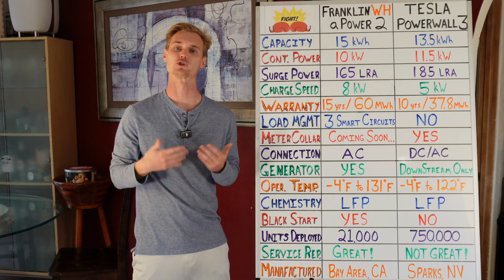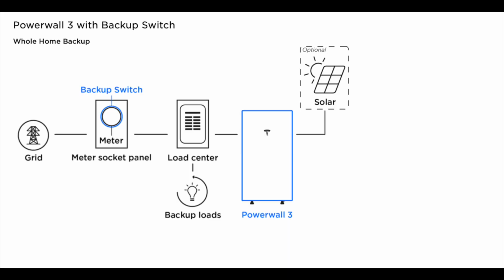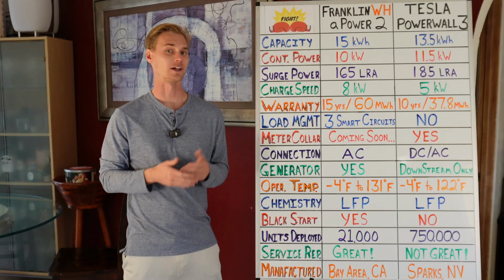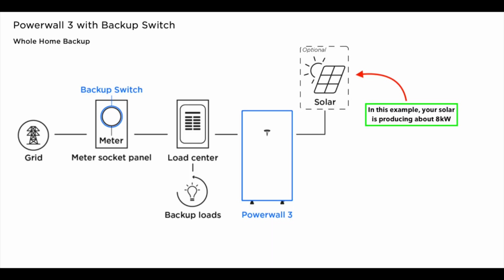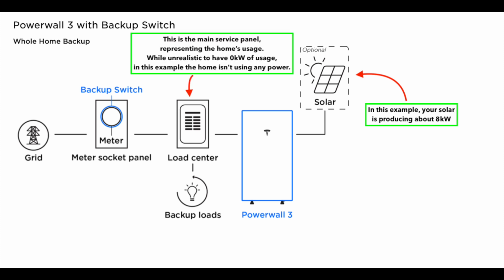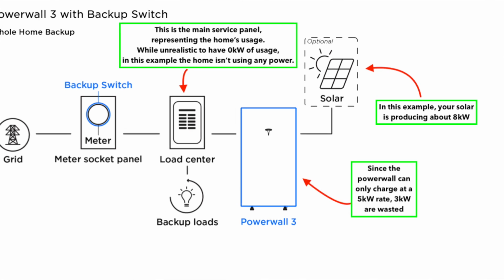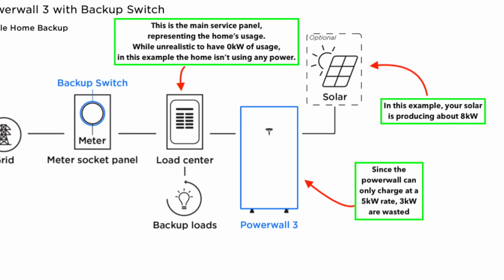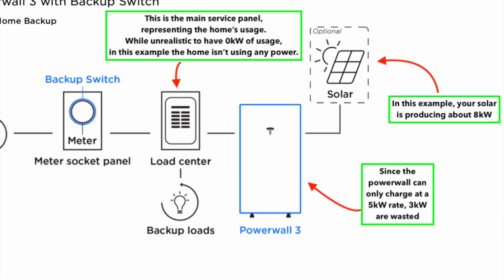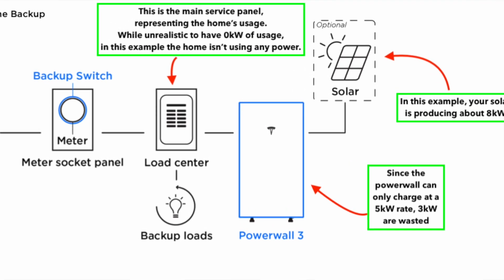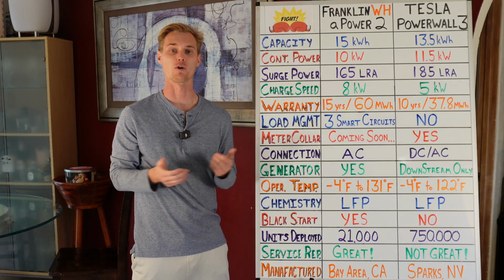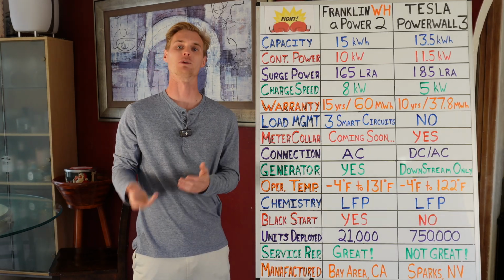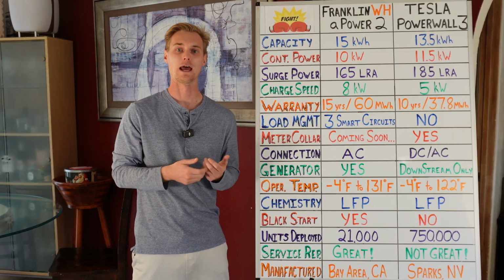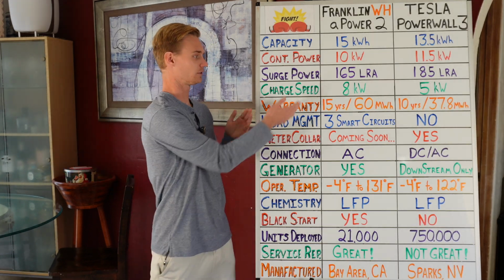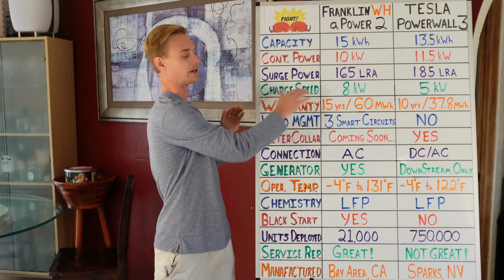For example, say you have a 10 kilowatt solar system, it's sunny, it's midday, and that system is producing about 8 kilowatts in AC power. If you're not home and the house isn't using much power, 3 of those 8 kilowatts would be wasted with the Powerwall 3, because the battery can't absorb it fast enough. With the Franklin, you'd actually capture more of that power, and less would be wasted.